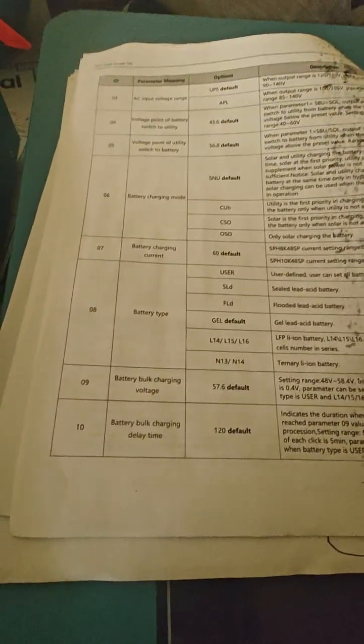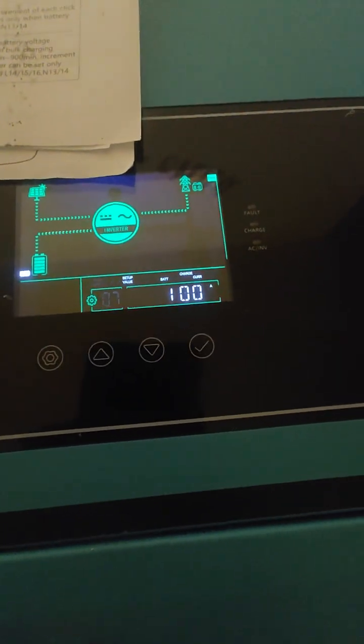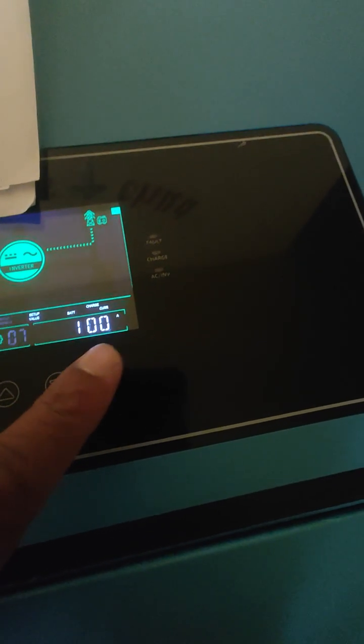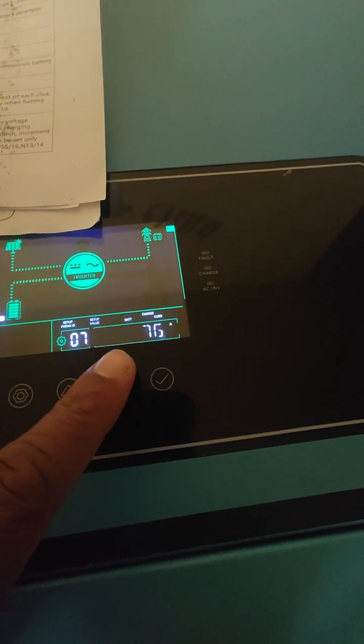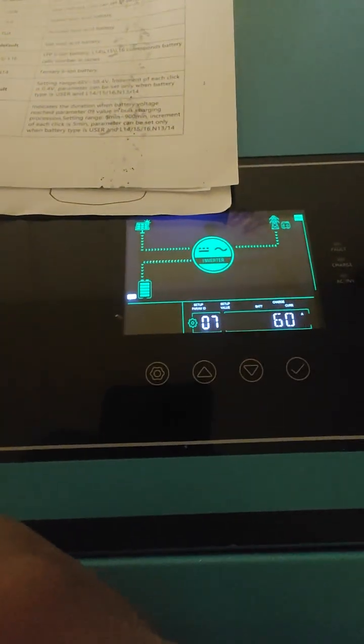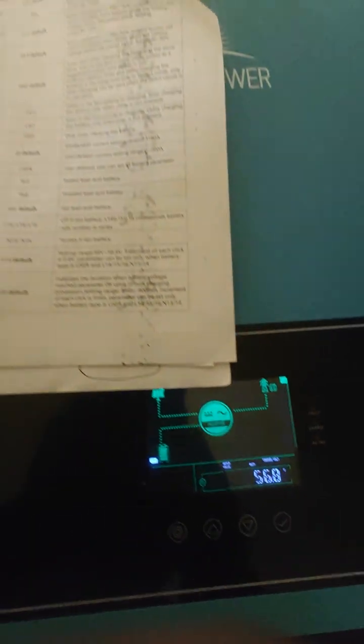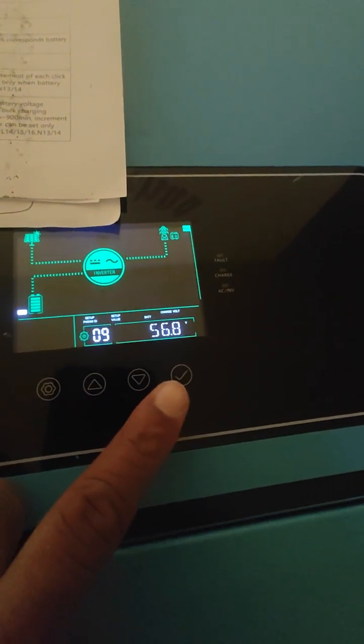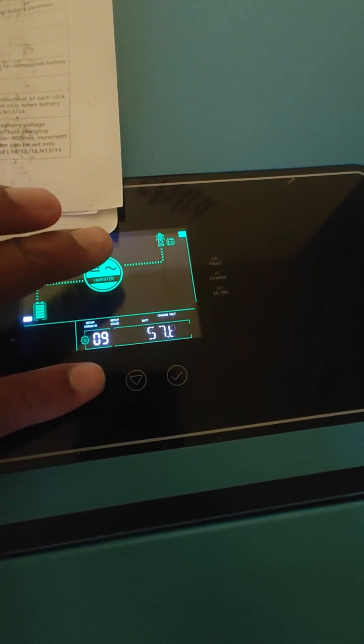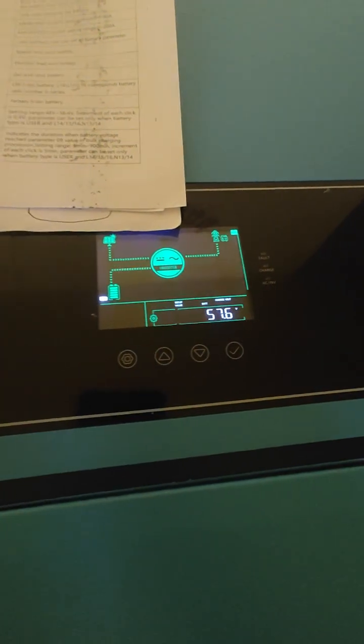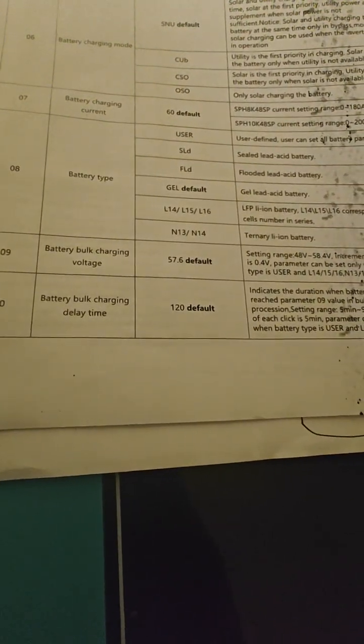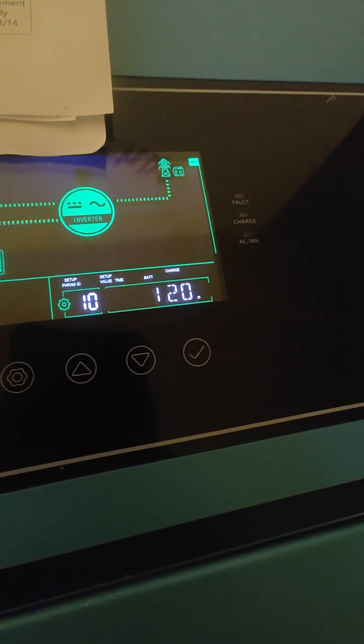Let's go to number 7, the battery charging current. Looks like 100 amps, so we'll take this back down to 60, which is the default. Then we can increase it from there. Battery type for number 8, L16, which is what is recommended for the SunGold batteries. Go to number 9, bulk battery charging voltage. Again, until I know what that means, I will have everything on the defaults. Number 10, bulk battery charging delay time. Set the default. So we'll take that.